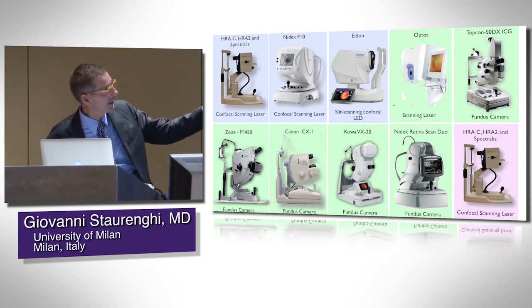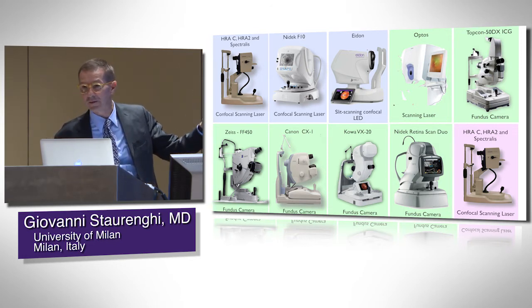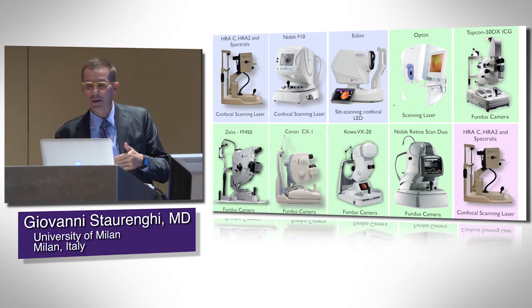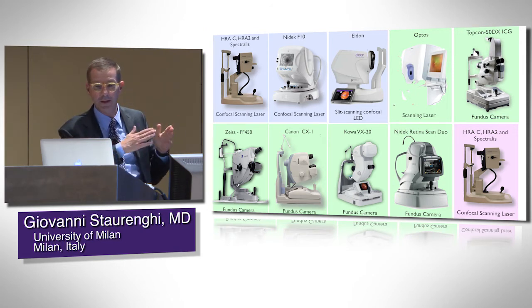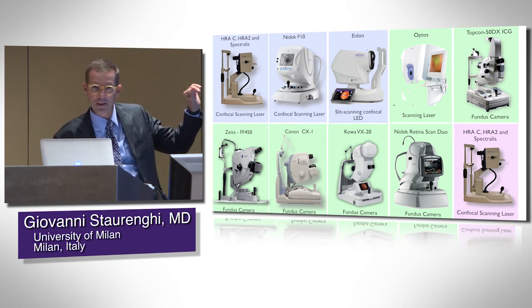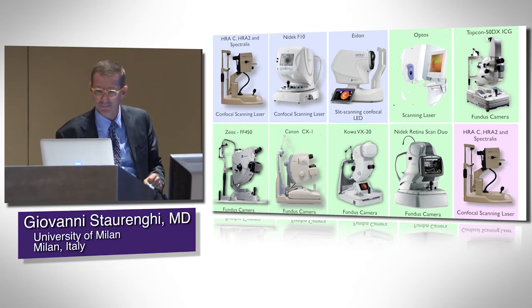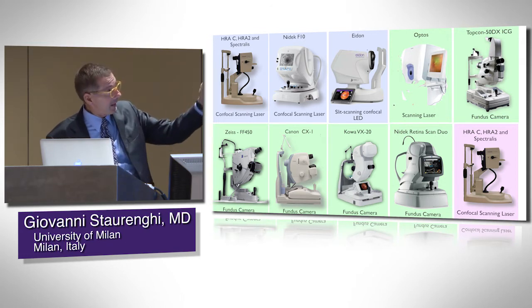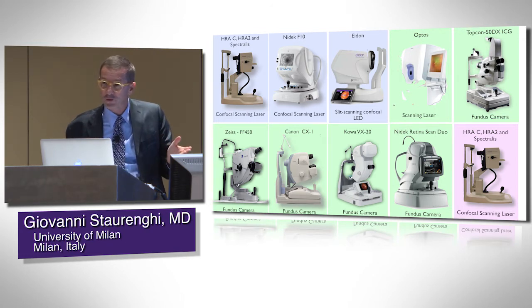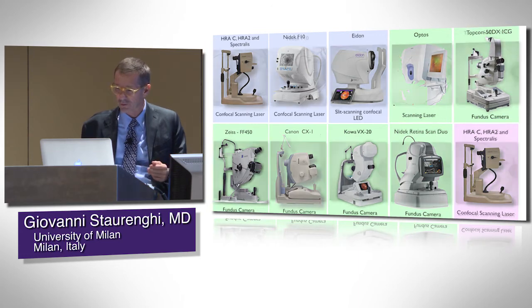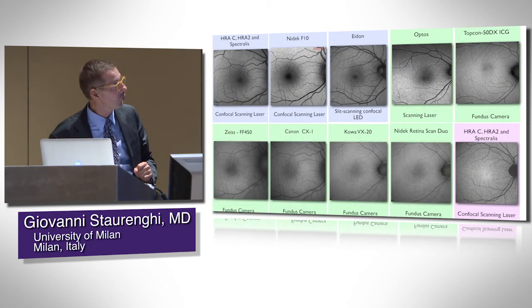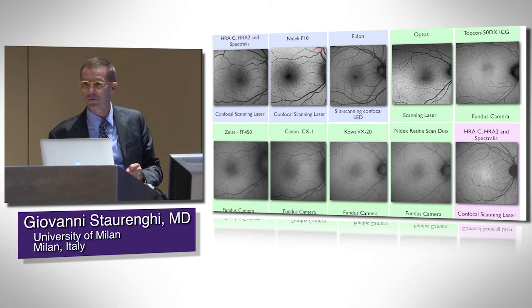This is why it's not just related to the scanning laser, but to the confocality. The Eidon is a slit-scanning confocal LED instrument — the difference is that instead of having a pinhole, you have a slit lamp. The scanning laser from Optos is not confocal, so it's not able to get blue autofluorescence; what you get is green autofluorescence. Here you can see the different types of fluorescence.